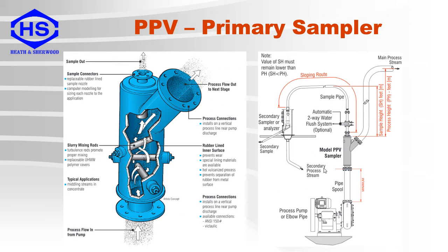This is an example of a pressure sampler with mixing bars which is called a PPV. These are used for slurry applications and are designed for vertical process lines which are under pressure. The mixing bars are optional and are used to mix the slurry for better sample representativity. The PPV has a nozzle placed in the middle of the slurry flow to extract a portion of the material. The extracted sample then goes through a sample exit nozzle, and the process flow exits the main body of the sampler at an angle.